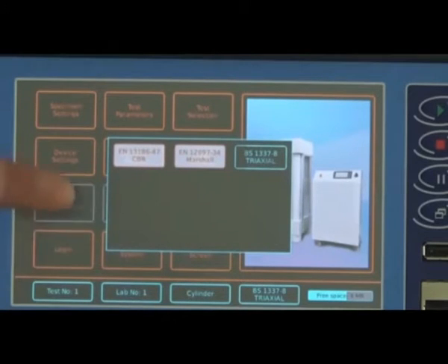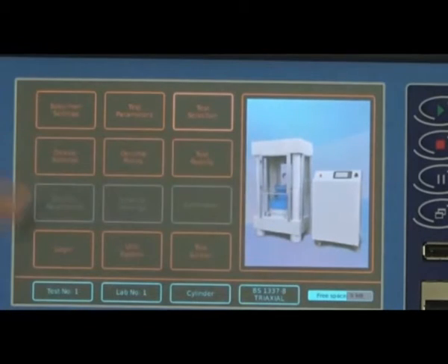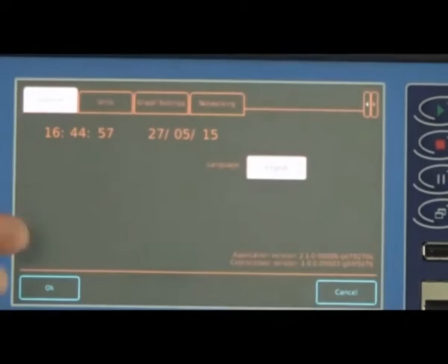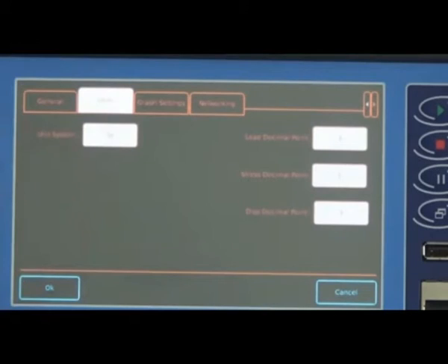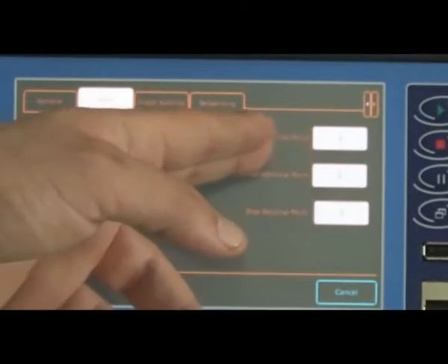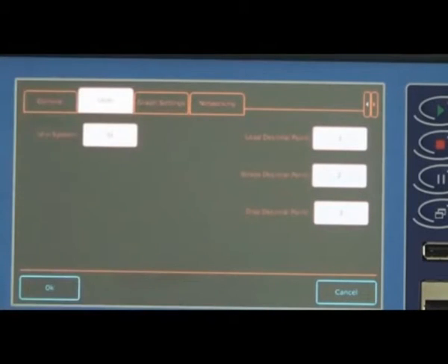The third option is the test selection. As you can see, you can select CBR, Marshall or Triaxial. Since we are going to conduct the Triaxial testing, we already initially selected the Triaxial. And the fourth one is device settings. Here in the general tab, you can set the time and the date and the language. And the second tab is units. It is initially selected as SI unit system, which is metric system. And the other menus are load decimal points, stress decimal points, and displacement decimal points, which are necessary significant figures that have to be selected before test.